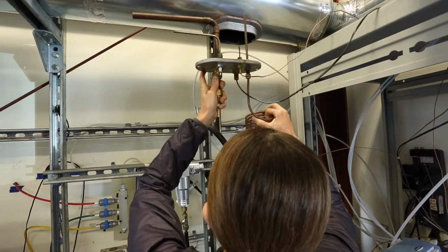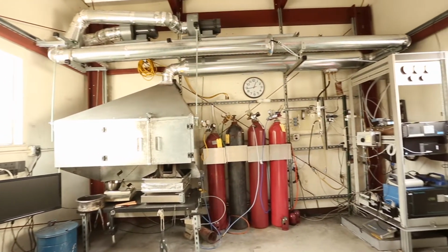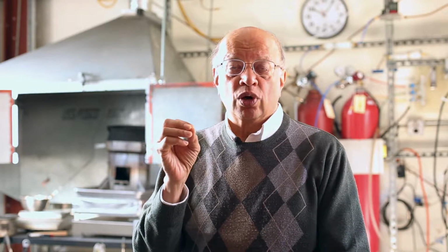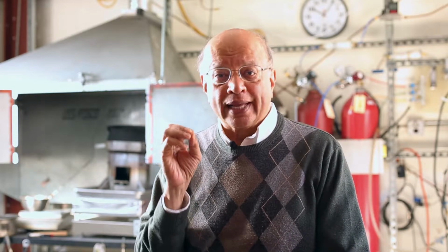In our approach, we focus heavily on great care in design of the lab, and we pay close and careful attention to good quality installation and inspection and then good operation of the core elements of all subsystems of the cookstove testing lab. We emphasize the importance of capturing all emissions, mixing those emissions well with clean dilution air, taking representative samples of pollutants and fuel, and collecting reliable and repeatable data.